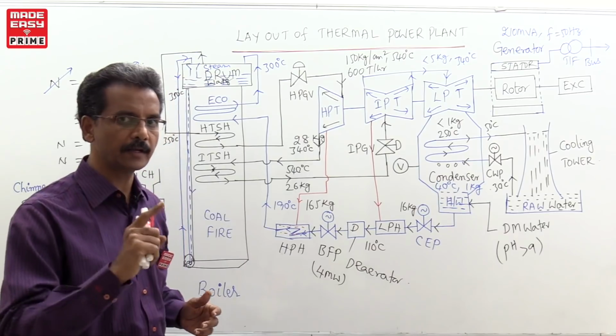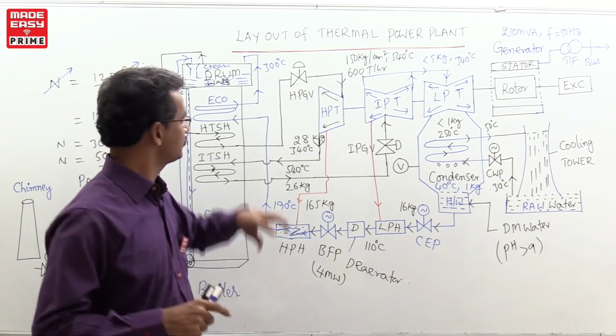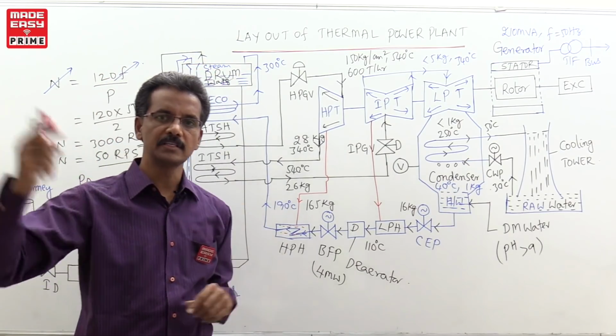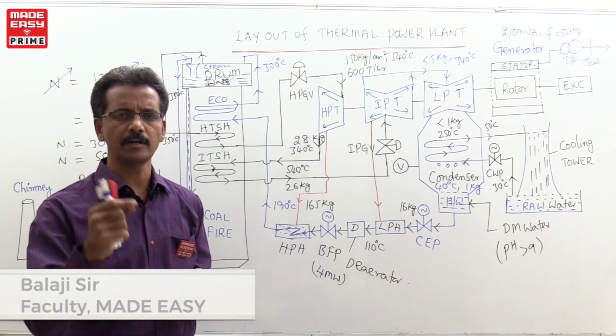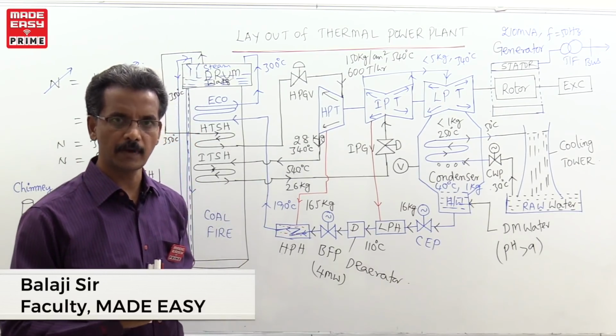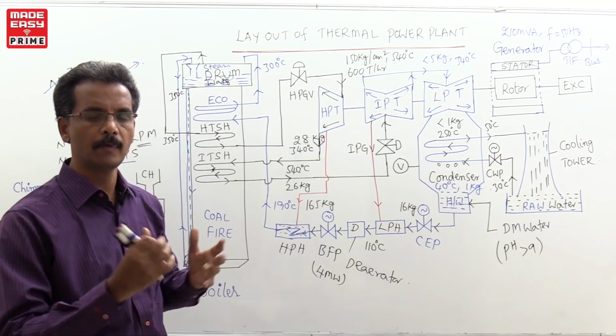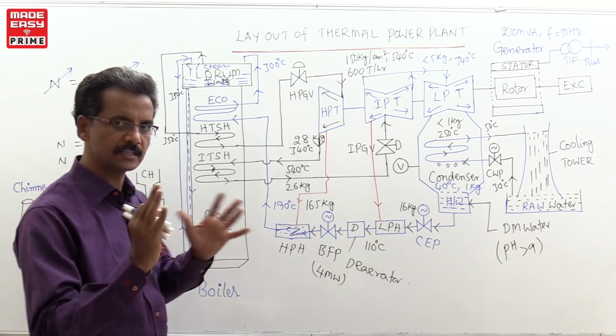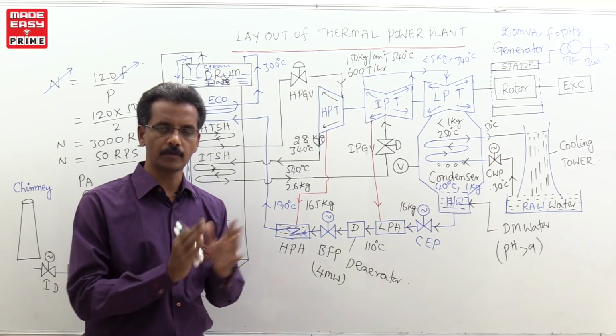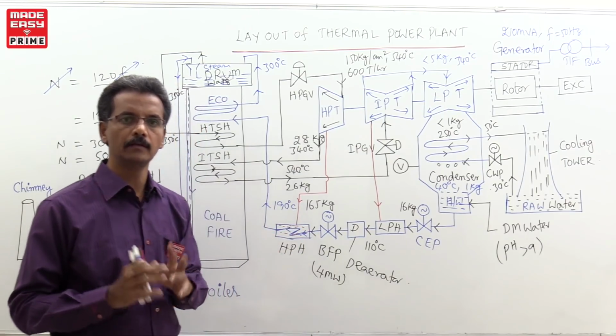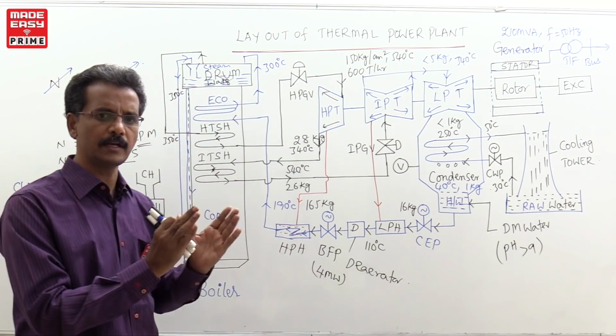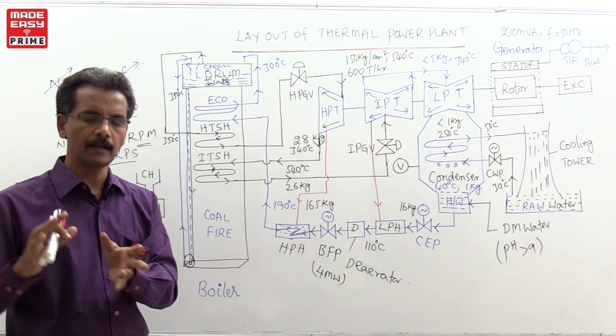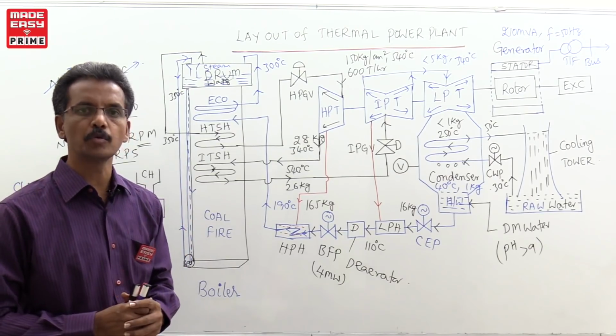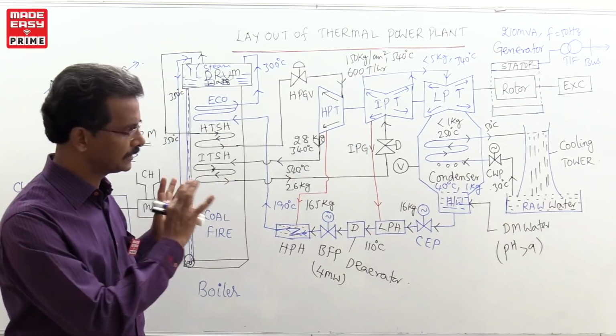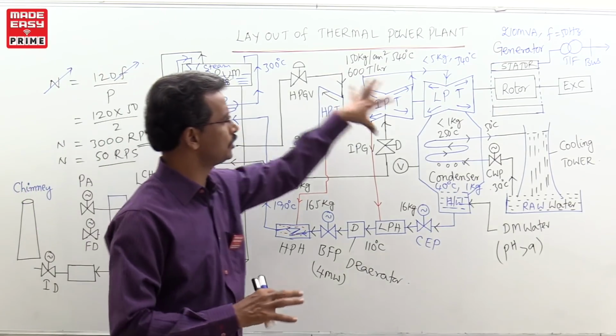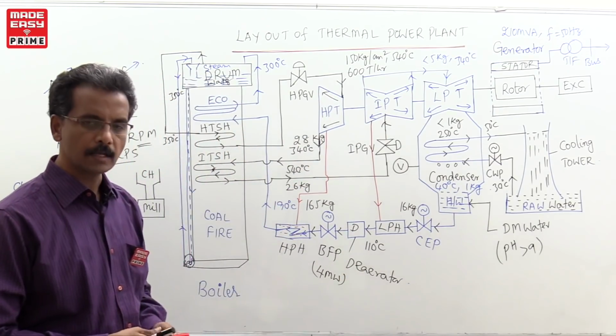Now, in the case of supercritical boilers, because the drum is not there, the efficiency comes to more than 40 to 43%, which you can expect in supercritical thermal plants. Okay, that is the basic difference. From the efficiency point of view, for subcritical you can think of less than 39 to 38%. In the case of supercritical thermal plants, it is 42 to 43%. This is about the simple process of the thermal plant on one side.